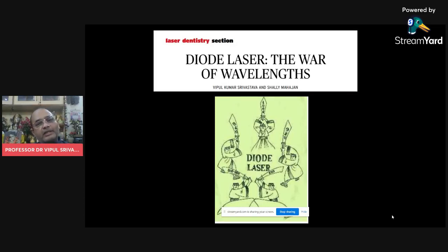So I wrote an article. This article was published in an Indian journal in the year 2014. The confusion is not with the hard tissue laser, not with the Nd:YAG, not with the carbon dioxide laser. The confusion is always with the diode laser, because they have so many wavelengths, and which wavelength we need to buy. That time we had 810 nanometer, 940 nanometer, 1064 nanometer, and 980 nanometer wavelengths. This is my original article.